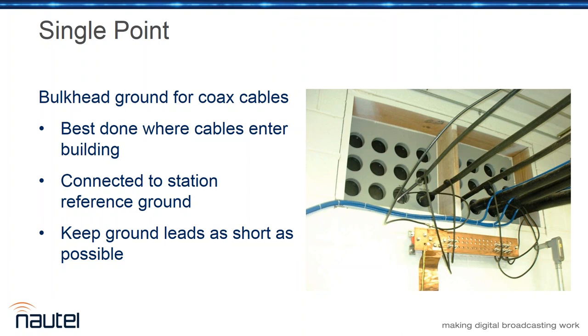The higher, the more surface area we can provide on our grounding, the better off it is, especially with the high frequency components where skin effect comes into play. So if you've got a choice between strap and cable, go with strap every time because you've got more surface area. Even a 2-inch strap has got more surface area than, for example, a 4-aught cable. Connect them to a reference ground, keep them as short as possible.